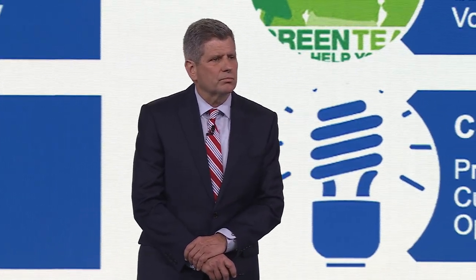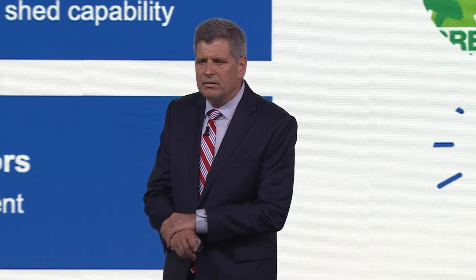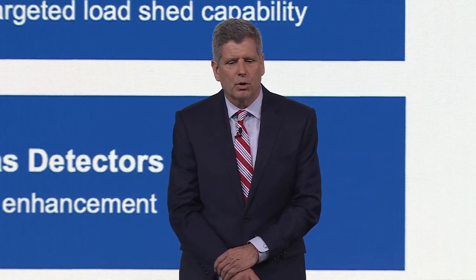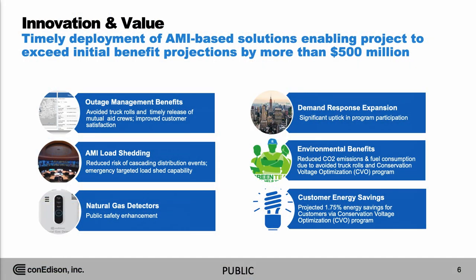All of these deliverables that we rolled out as we ramped up the project early in the program have driven up benefit projections. Not only does the AMI system allow us to monitor consumption, it also allows us to improve the efficiency of operation of the grid. Through our conservation voltage optimization program, we are projected to save our customers about 1.75% in electricity. That's a huge savings in both energy and emission reductions.